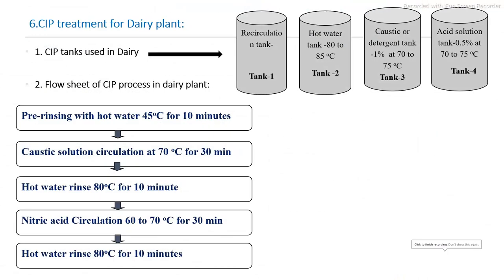For CIP application in the dairy processing plant, before starting milk processing, CIP treatment must be carried out first, and after completion of each batch, CIP treatment is again carried out. Each and every batch requires CIP treatment both before start and after completion. The concentration of caustic solution or acid solution depends on the contamination level of the food soil; in dairy processing, the concentration is mostly in the range of 0.5 to 1 percent.